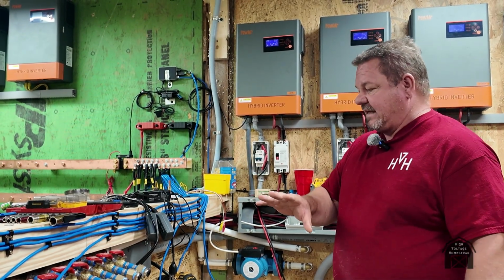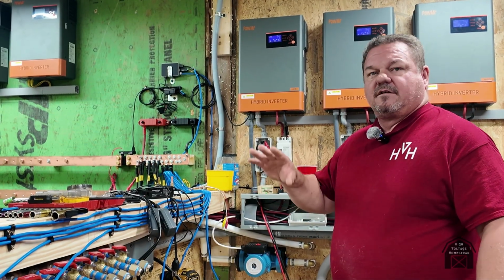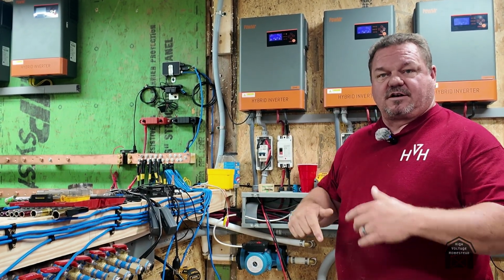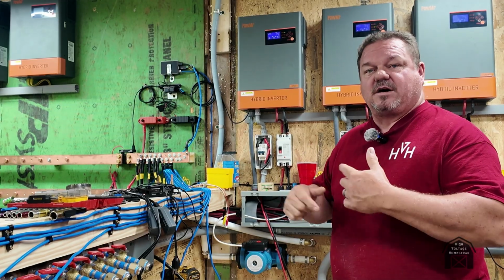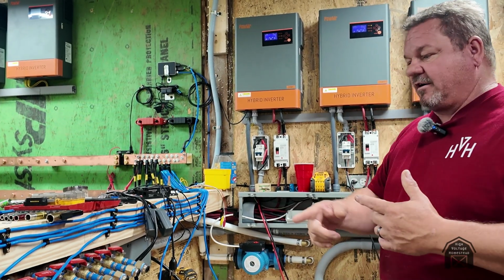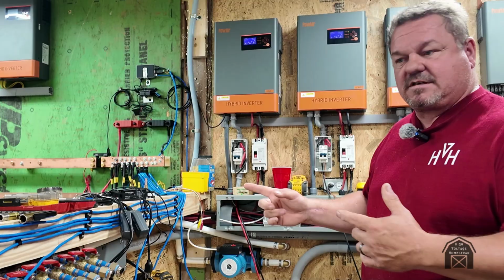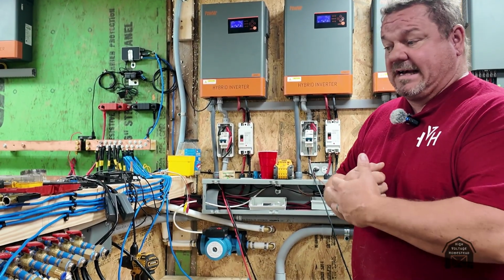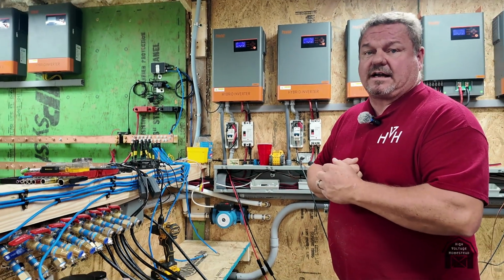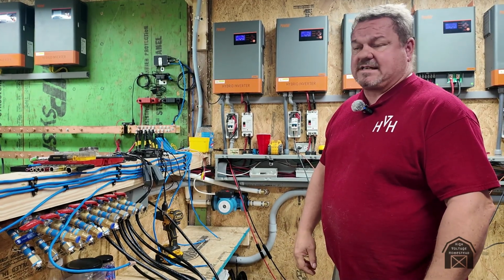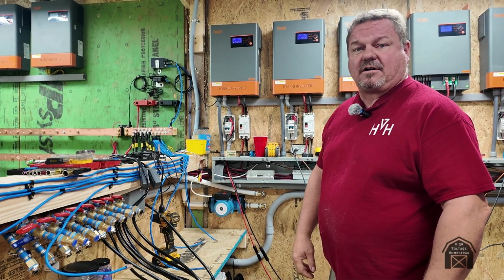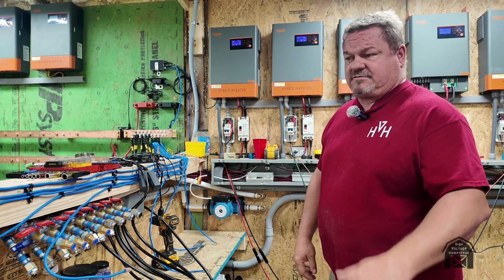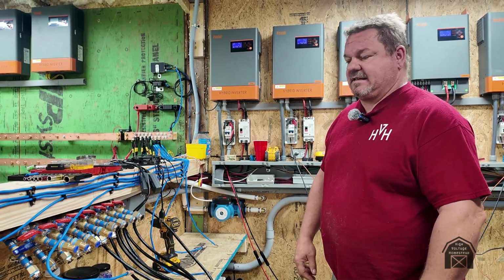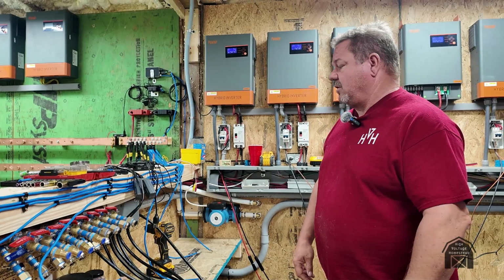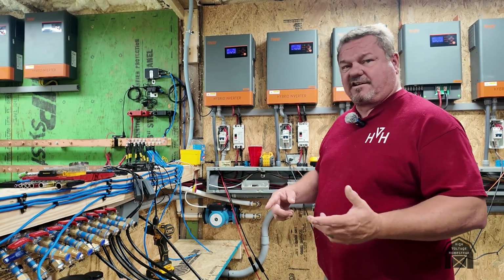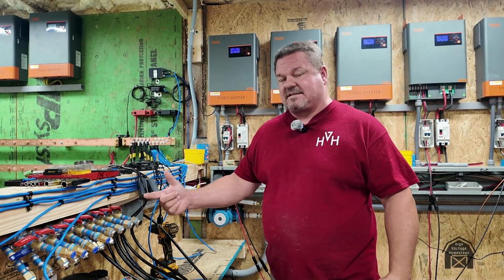They will turn the main water pumps that circulate the spring water on, so it'll let it run on the glycol loop starting up so everybody can be warm, because I've noticed these things do not like starting. If you pump 60-degree spring water through them and turn the power on, they shut down almost every time. They think it's too cold. So this will let it just recirculate the glycol and keep an eye on the temperature.